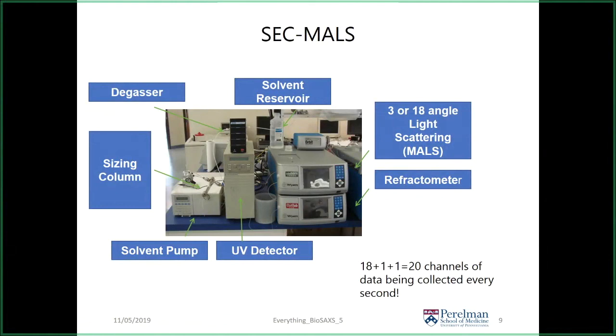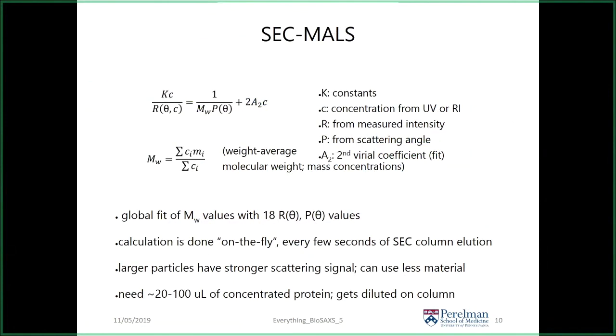The eluent then goes into the differential refractometer. The dn/dc of protein regardless of sequence is always approximately 0.185 mL/g, and you can relate that differential refractive index to an absolute protein concentration — it's more reliable than UV extinction coefficients. So at each one-second time slice you have up to 18 angles of light scattering, sometimes inline dynamic light scattering, and a concentration readout along the gel filtration trace. From this, you can calculate absolute molecular mass, and this calculation is done on the fly every second.